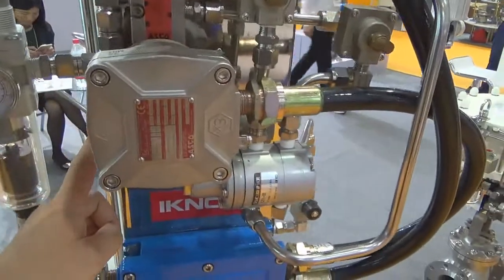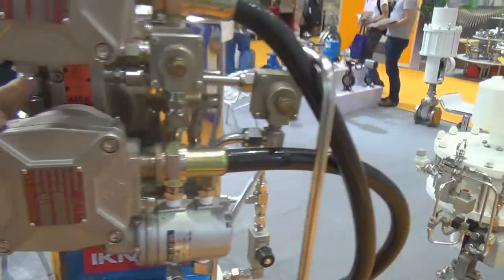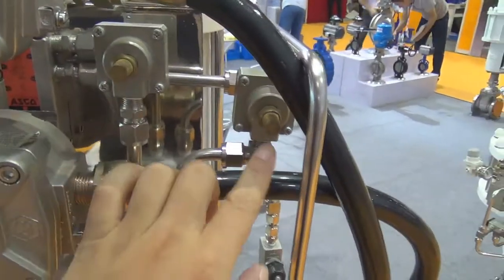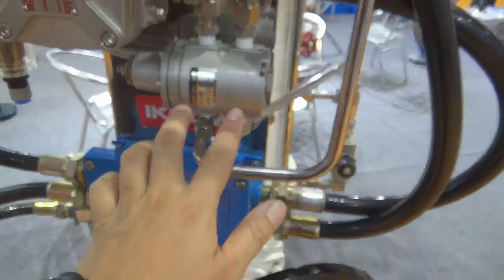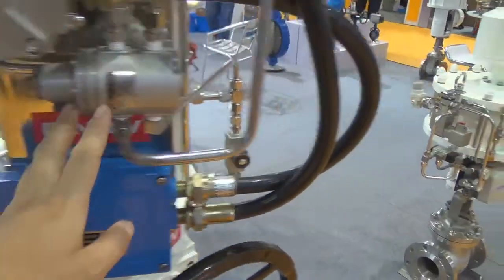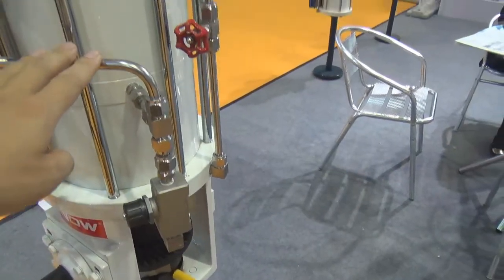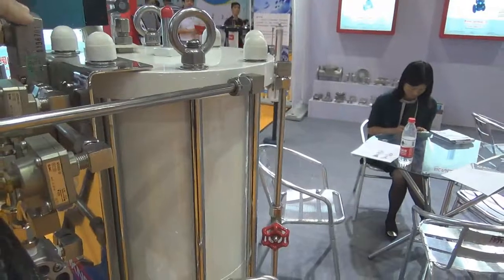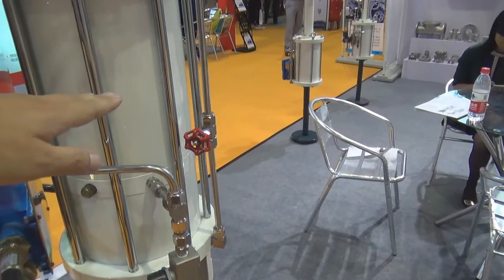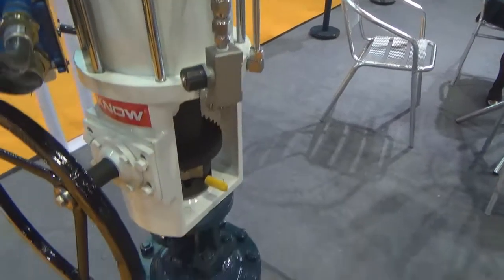When the system has gas, the lock valve will open. And then the solenoid valve has two-way flow outside. This is one way and another. The two ways will flow through the lock valve because the lock valve was already opened by the gas. So we have two-way flow to the cylinder, upside and downside. So we can use the solenoid valve to change the gas flow to the upside or to the downside. So we can control the piston inside the cylinder to move up and move down to control the valve.